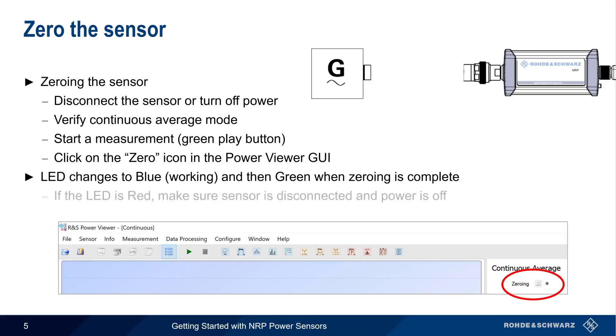Note that if the LED turns red, this means zeroing was aborted, most likely because power was still being applied to the sensor.